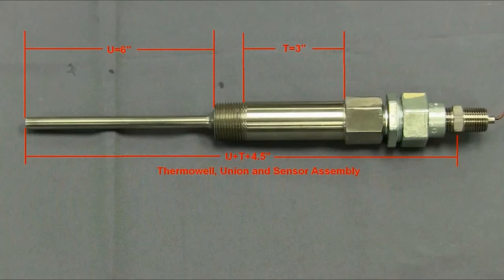The known or fixed lengths are the thermowell hex and thread, the union coupler, and the spring-loaded sensor hex. These total 4.5 inches. The factory would then go and order a sensor with an overall length of 13.5 inches.